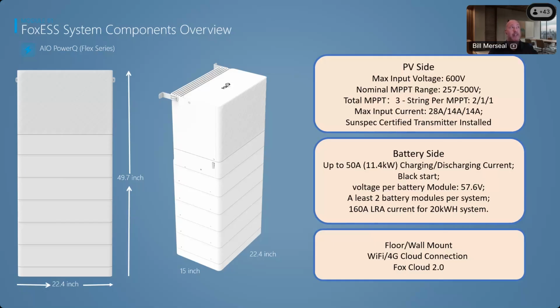So it's a parallel string, which is why you'll see the max input current at 28 amps versus 14 and 14. There are 2 strings here, and we have the SunSpec certified transmitter installed on each of these systems.